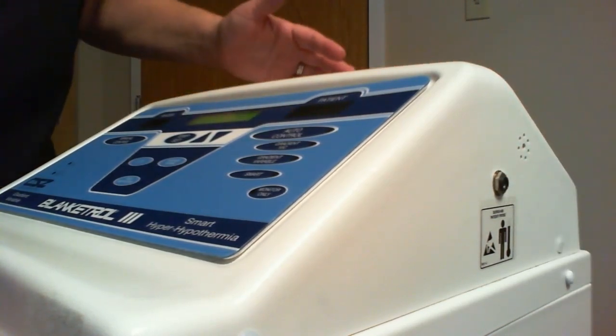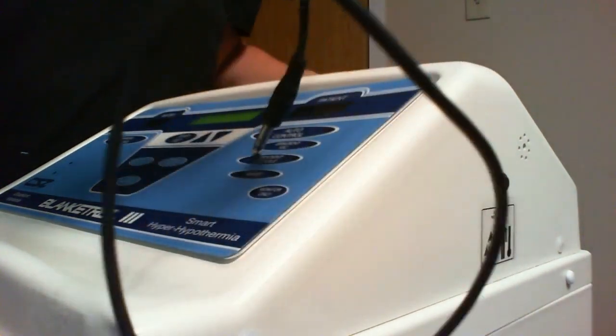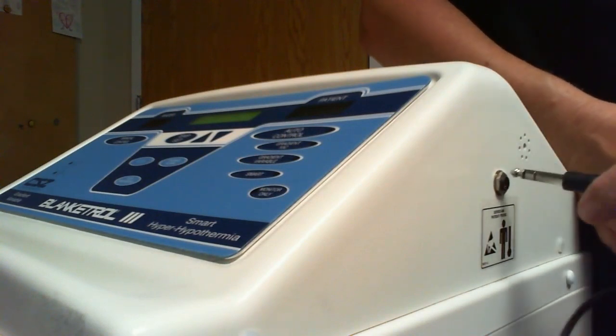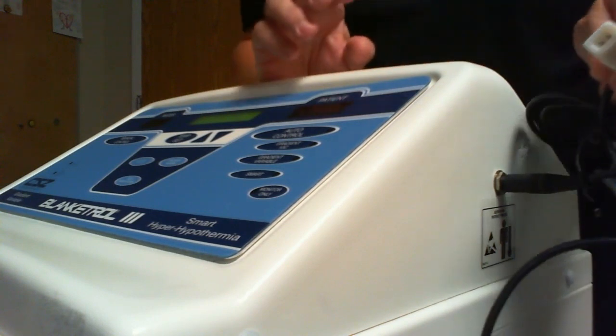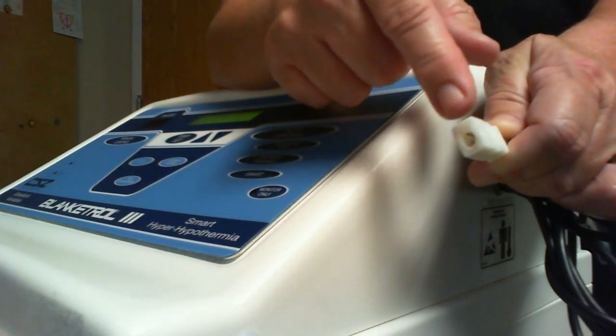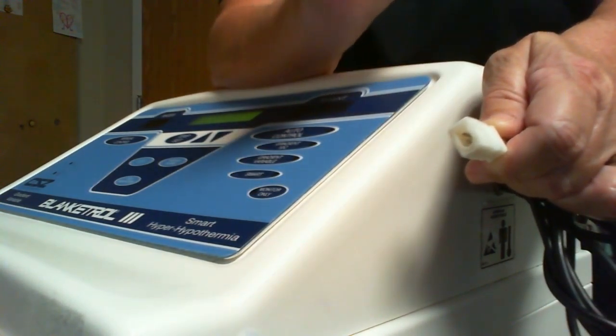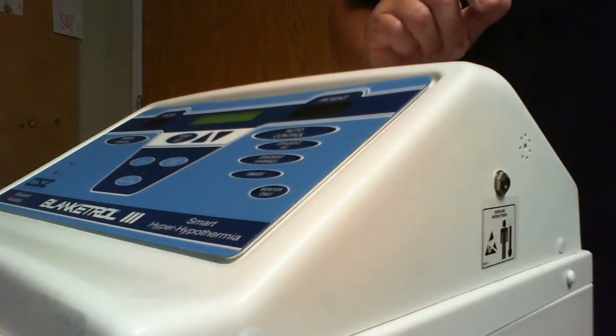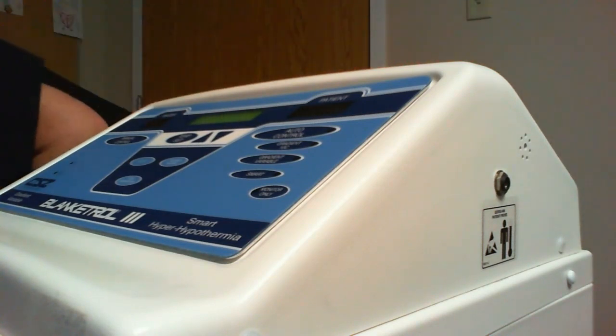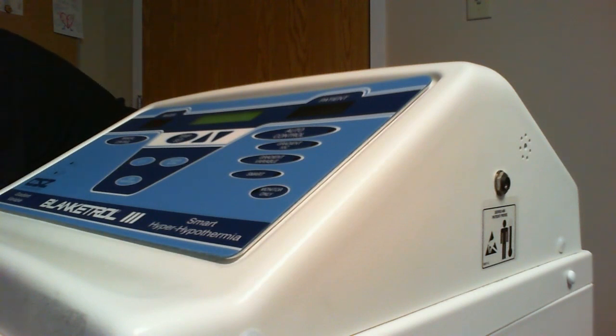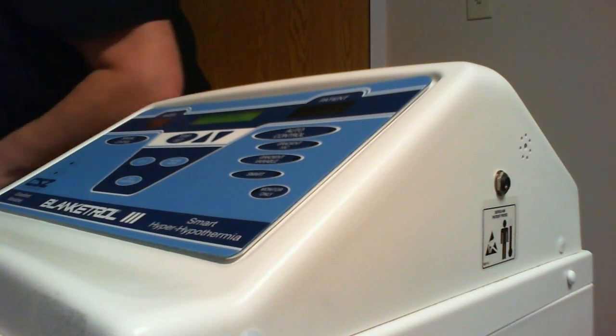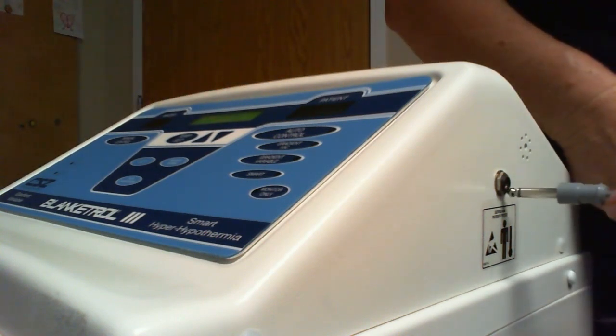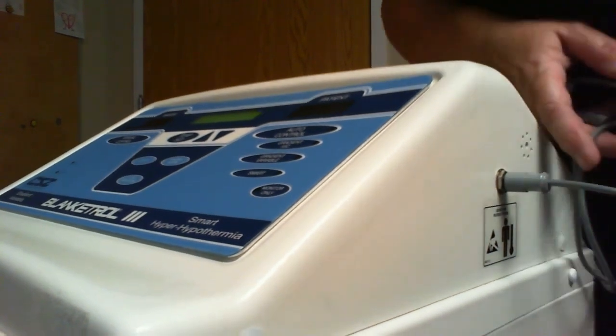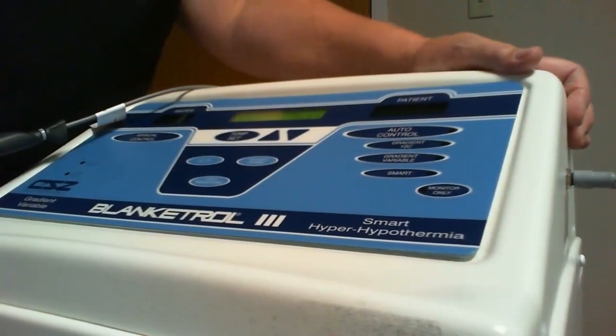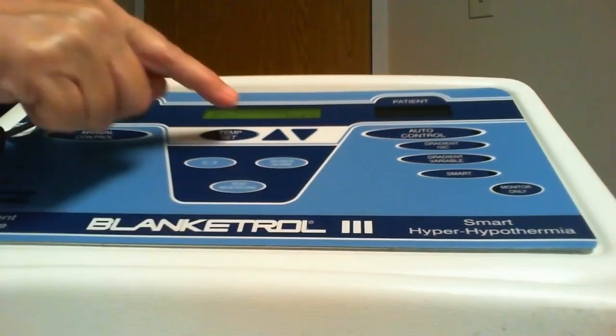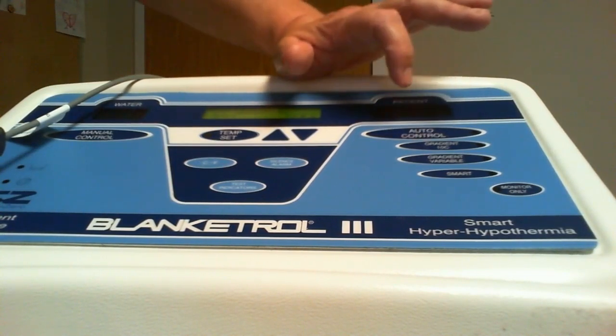And I am going to look in here, the little front opening, and I'm going to get the cable that friction fits into the side of the machine. And then the other end will connect to either your esophageal probe or your Foley catheter, however you are measuring your temperature. What I'm going to do is insert my simulator. I'm going to insert my simulator in the side here so that I can simulate patients' temperatures. And so I'm going to go back to my setup.